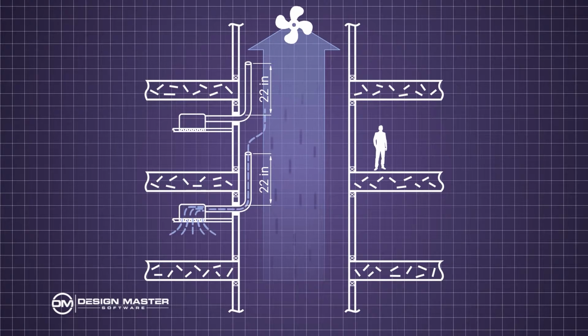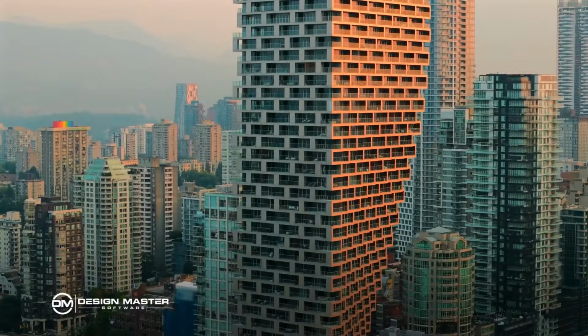Okay. The air comes in here and goes up that way, and then leaves from the roof. Simple as that. The idea is that the air cannot go backwards. There's no way that the air could go from here and turn around and go back down from this floor to that floor. That's a subduct. The concept is that the air rushing vertically past the subduct will not have any opportunity to go back down the subduct and into the floor above or below. And this is how you avoid the fire smoke damper. This is commonly, as I say, seen in hotels and apartment buildings.